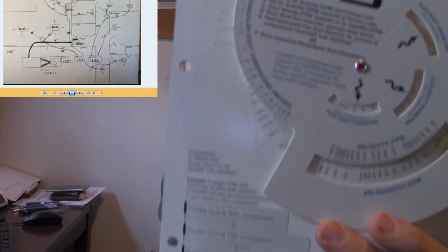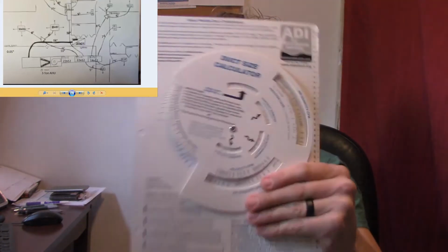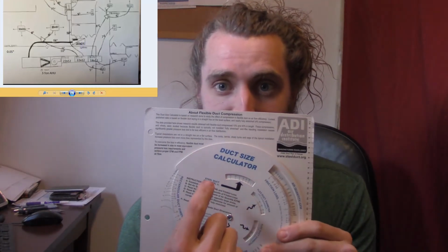If your guys are not stretching their ductwork out straight, if they're putting any bends in it, sags in the support system, anything like that, I would generally use the 15 or most often the 30% compression. Now, let me give you an idea of what this looks like. So, 6-inch round. How many CFM can you get through a 6-inch round? Well, we all know that you can get 120 CFM through a 6-inch round, right? Well, that's because we are all sizing it at 0.1 friction rate, which we know doesn't work because you watched my last video. 0.1 doesn't work all the time. Sometimes it does, but for the sake of argument, let's say that we are designing our system at 0.1 and we are squeezing 120 CFM through a round steel duct.